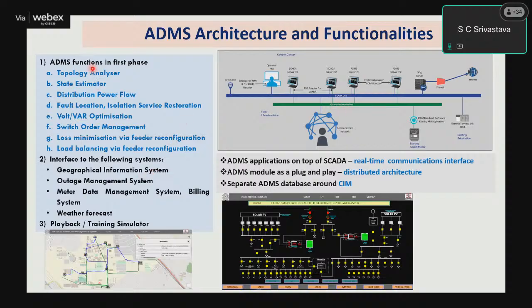It performs many tasks like complete system analysis of the state, power flow, fault location isolation, volt-var optimization. We had also put smart inverters, which also participate in volt-var control, loss minimization, and then it has a geographical information system. You can see the cables, where they go, what the status is, outage management, weather forecast, and load forecast we are doing. It is being used for training purposes also.